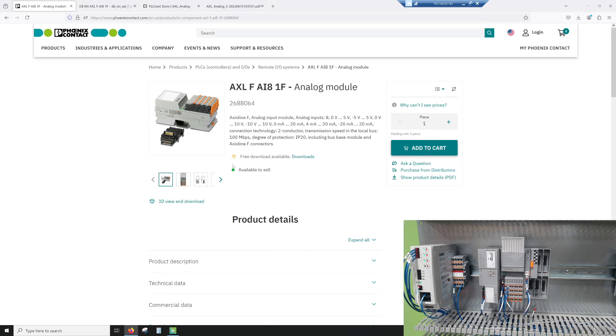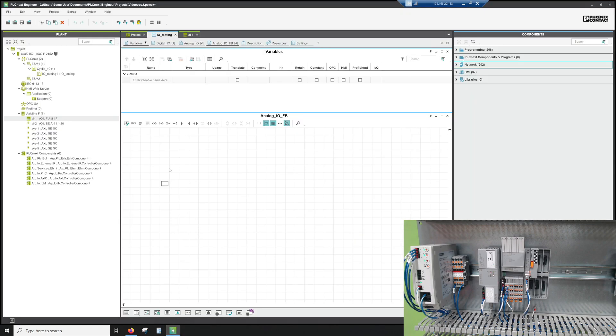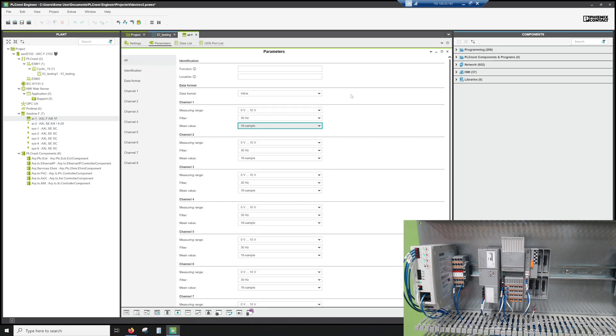Today we're going to look at the AXL AI8, which has voltage and current inputs. In the project you can see it's already loaded, along with smart elements that will be covered in another video. One key difference between the two is this one is voltage and current and also 15 bits plus a sign, while the smart elements is zero to ten thousand, so only about 12 bits. Depending on your accuracy requirements, you may want to go with the AI8 or the smart elements.